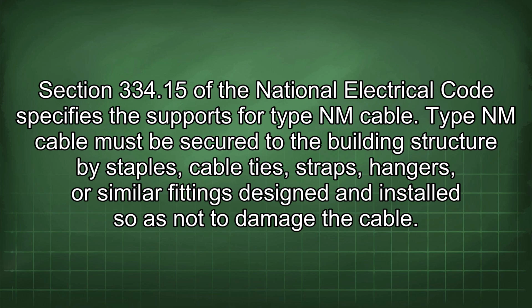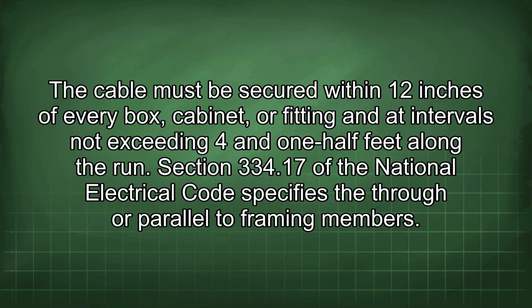Section 334.15 of the National Electrical Code specifies the supports for Type NM cable. Type NM cable must be secured to the building structure by staples, cable ties, straps, hangers, or similar fittings designed and installed so as not to damage the cable. The cable must be secured within 12 inches of every box, cabinet, or fitting and at intervals not exceeding 4 1/2 feet along the run.